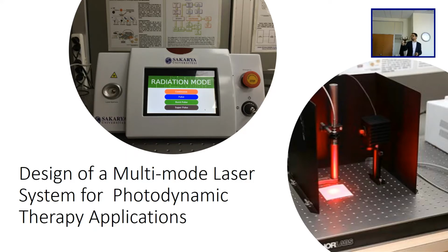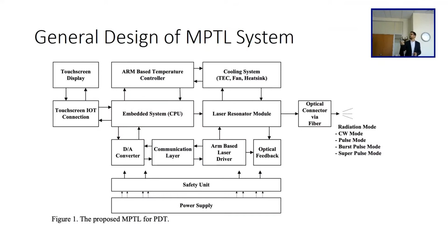So you have to make a touch screen, which is your input module. So we used a microcomputer, which is maybe a Raspberry Pi 3, I believe. And then we use two separate ARM-based microcontrollers. One of them is for the cooling system. This is thermoelectric cooling using some elements I will show you. And the other one is for the laser driver. Laser driver means you have to make a constant current supply. It should be constant because you don't want your output to fluctuate. You need stable power output there.